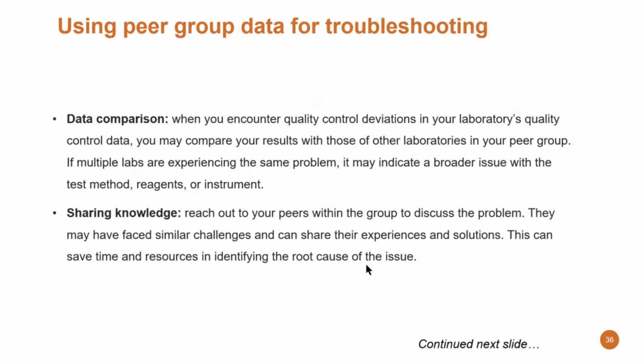Using peer group data for troubleshooting: data comparison. When you encounter a quality control deviation in your laboratory, you may compare your results with those of other laboratories. So that's the beauty of the peer group. See how the others are performing. If multiple labs are experiencing the same problem, it may indicate a broader issue with a test method, reagent, or instrument. Sharing the knowledge: reach out to your peers within the group to discuss the problem. They may have faced similar challenges and can share their experiences and solutions. So this can save time for you and also resources to identify the root cause of your out of control situation.